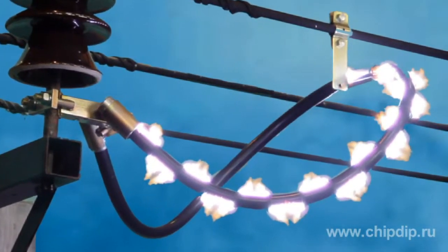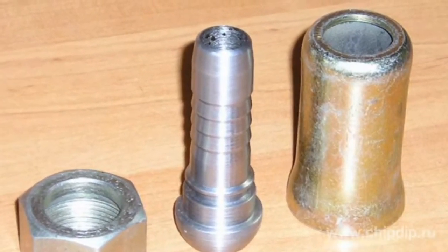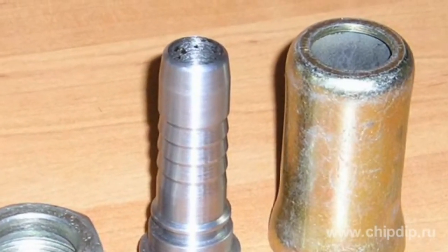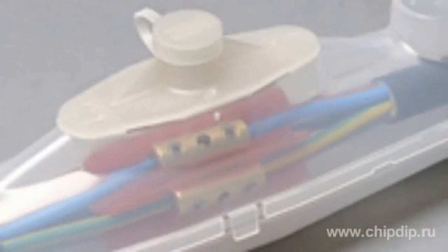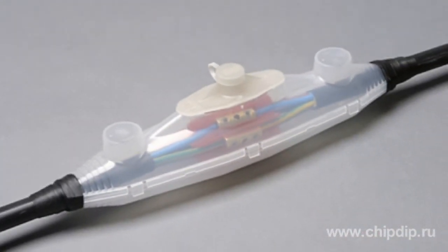To make the non-detachable connections, special crimp barrels or joint boxes are used. They can be not only crimped, but also filled with solder. Sometimes these connections are also called tight joints, as if to emphasize their increased reliability. It is worth noting that the used sleeve must necessarily correspond to the applied section of the wire to ensure maximum mechanical strength of the connections.